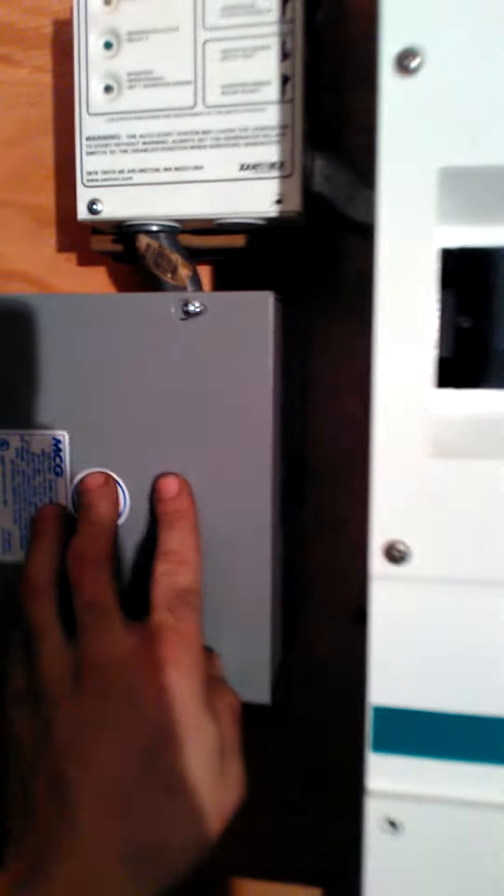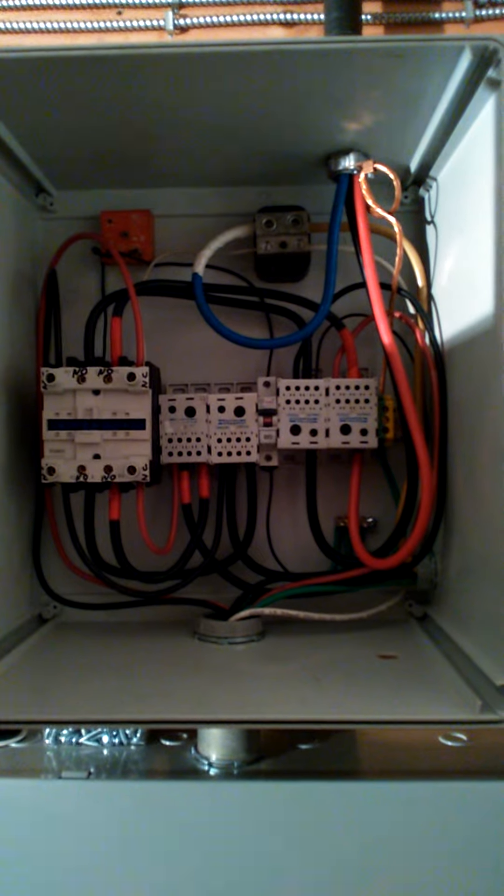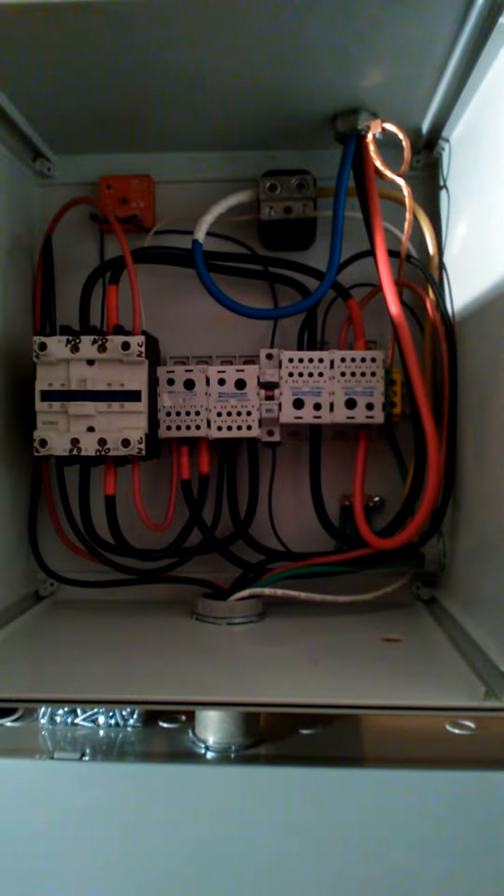The relay contacts are in there to open the louvers on the wall over there for the generator. And here's my relay contact box to bypass the inverters while the grid is still available.